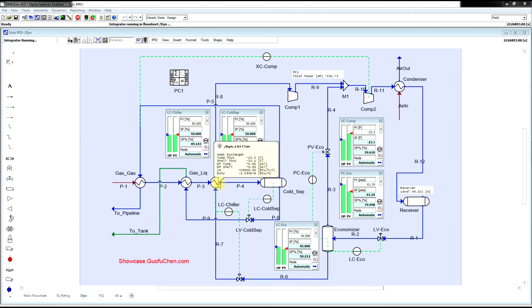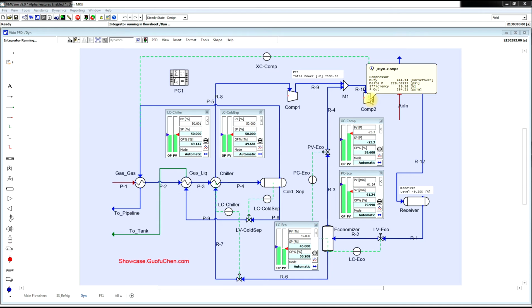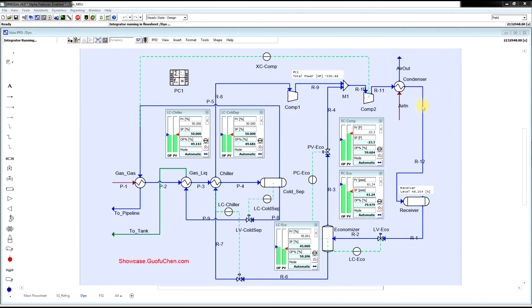The refrigerant in the chiller is vaporized and then sent to the first stage of the compressor. After combining the vapor from the economizer, it is further compressed in the second stage. After it is fully condensed in the air condenser, it is sent to the receiver.